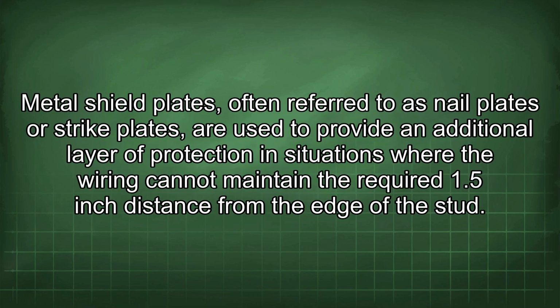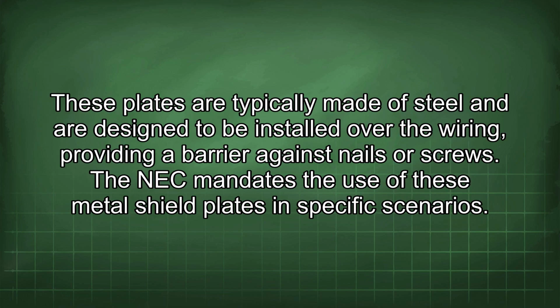Metal shield plates, often referred to as nail plates or strike plates, are used to provide an additional layer of protection in situations where the wiring cannot maintain the required 1.5-inch distance from the edge of the stud. These plates are typically made of steel and are designed to be installed over the wiring, providing a barrier against nails or screws. The NEC mandates the use of these metal shield plates in specific scenarios.